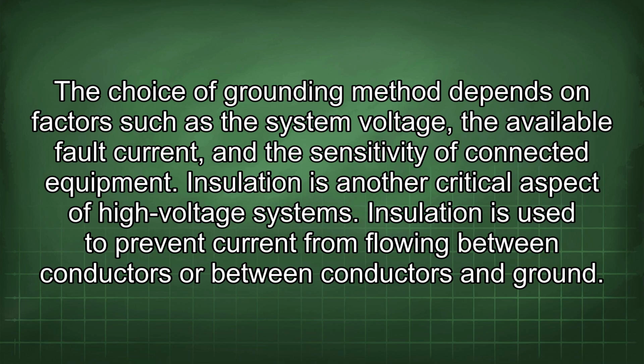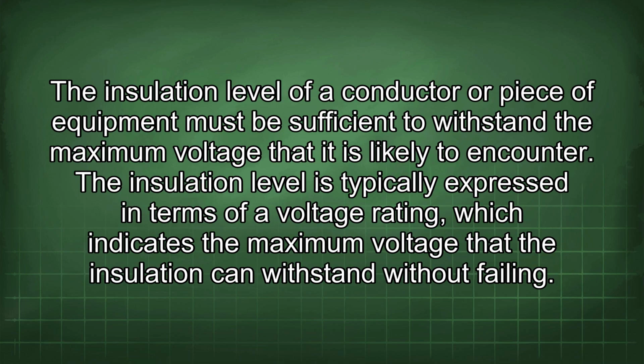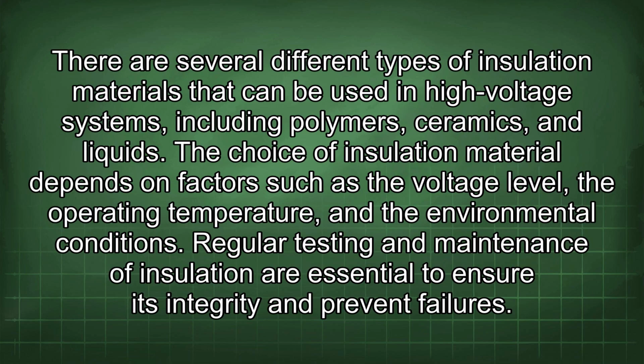Insulation is used to prevent current from flowing between conductors or between conductors and ground. The insulation level of a conductor or piece of equipment must be sufficient to withstand the maximum voltage that it is likely to encounter. The insulation level is typically expressed in terms of a voltage rating, which indicates the maximum voltage that the insulation can withstand without failing. There are several different types of insulation materials that can be used in high-voltage systems, including polymers, ceramics, and liquids. The choice of insulation material depends on factors such as the voltage level, the operating temperature, and the environmental conditions.